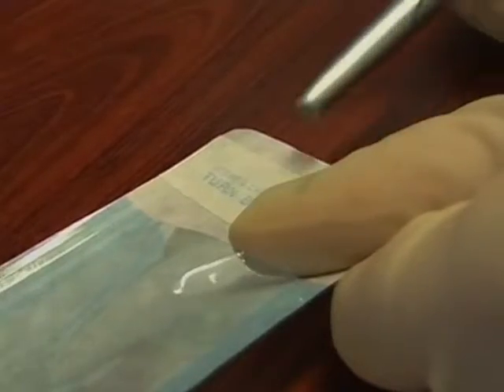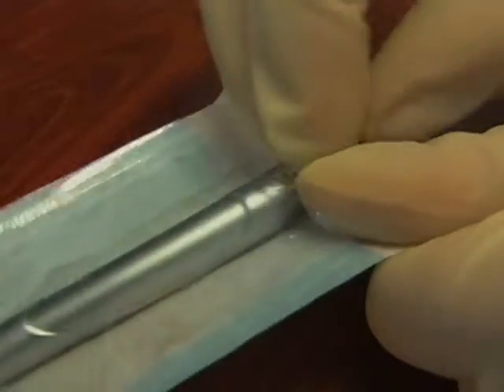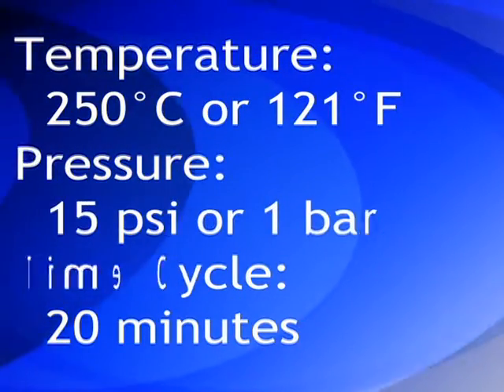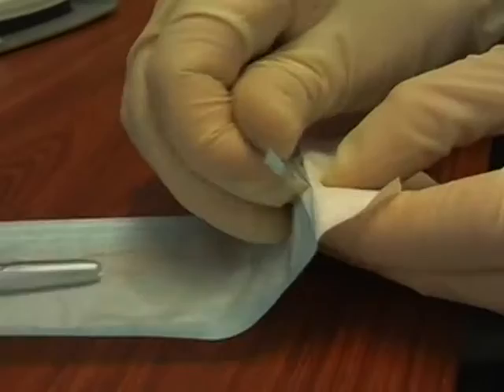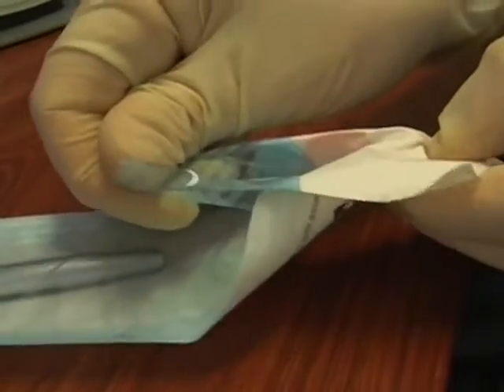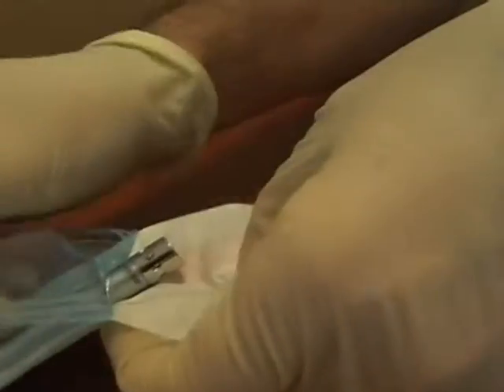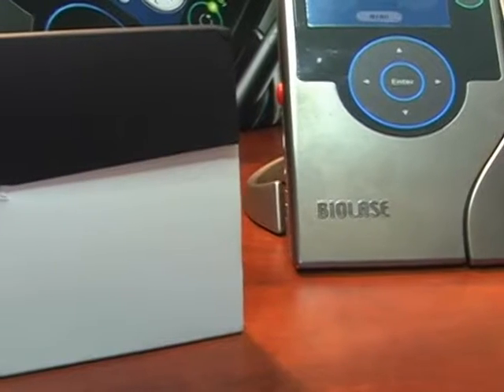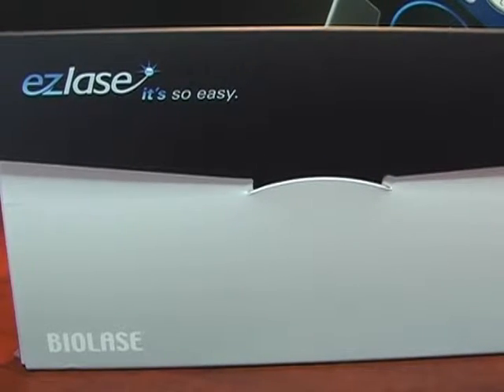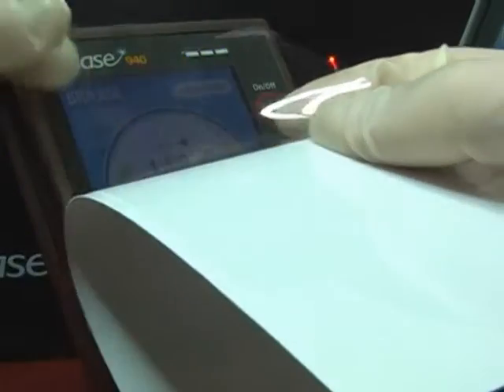It can be bagged and sterilized in an autoclave according to the suggested parameters noted in your user manual. A second handpiece is provided so you can continue to use your Ezlase while the second handpiece is subjected to a sterilization cycle. The Ezlase is supplied with a pack of plastic covers for the touchscreen. A new cover should be fitted before each procedure.